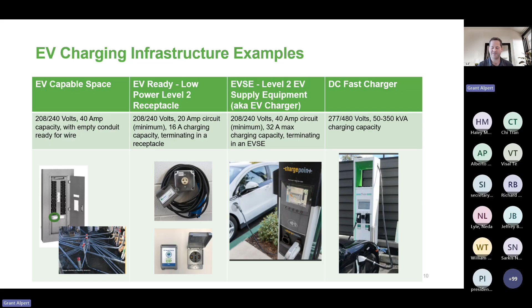And then there's the DC fast charger, which is much higher capacity, 30 to 50 to 350 kVA, at 480 volts. EVs have an onboard charger that converts AC to DC current using the level 2 or level 1 EVSE's supply. A DC fast charger has the inverter on the charger itself, which bypasses the onboard charger and starts charging the battery directly. So it's a little more efficient, at the cost of the charger being much more expensive.